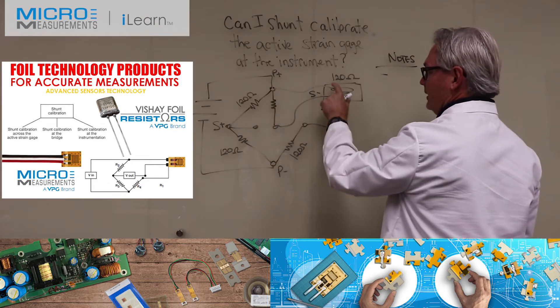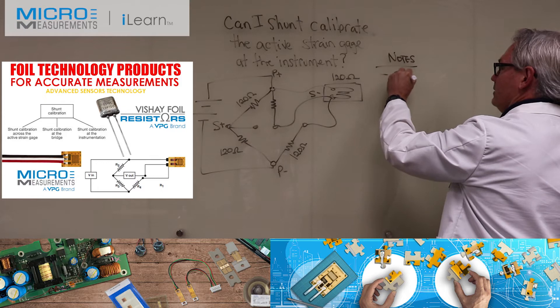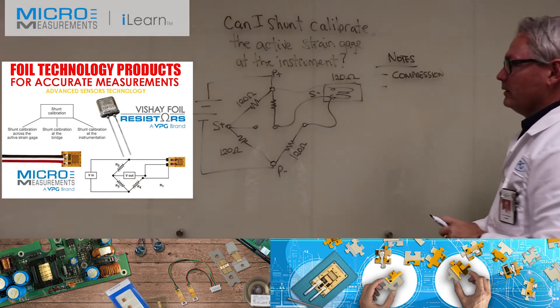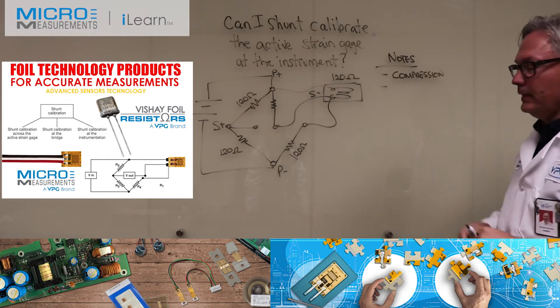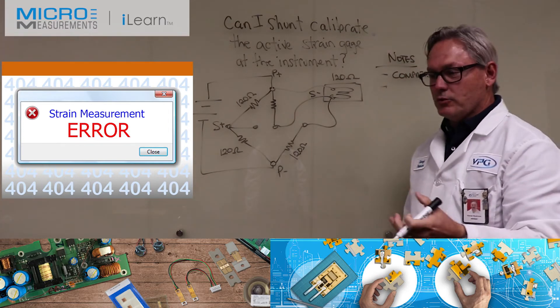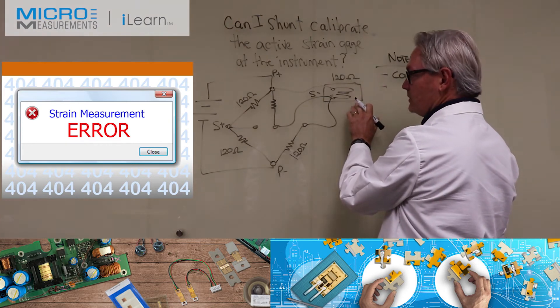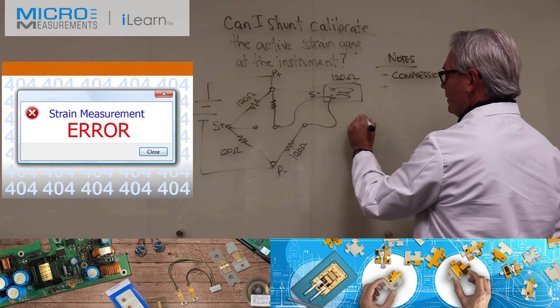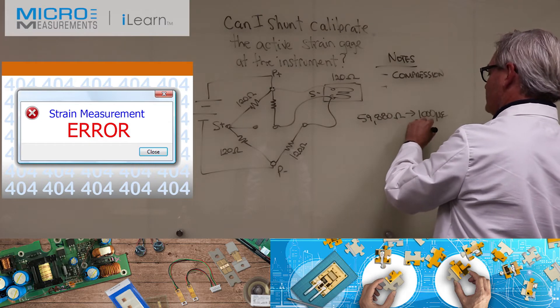First thing you should find is that since we're shunt calibrating the active gauge, causing that resistance to go down, it's going to simulate compression. However, there's an issue, and the magnitude of this problem is going to be a function of the resistor value of your strain gauge as well as what the calibration resistor is.